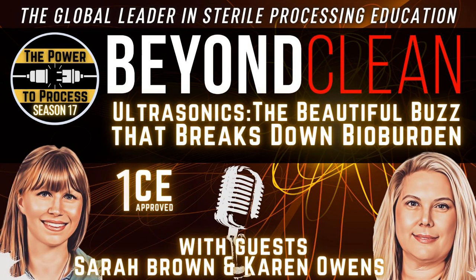Another important thing to consider is to avoid stacking trays for a similar reason. Most ultrasonics have the transducers that supply that ultrasonic energy mounted to the bottom of the tank. If one tray is stacked on top of another, the ultrasonic sound waves can't reach the top tray. Some multi-level sonics on the market do have transducers mounted to the sides to make sure that ultrasonic cleaning action can reach multiple levels of instruments.